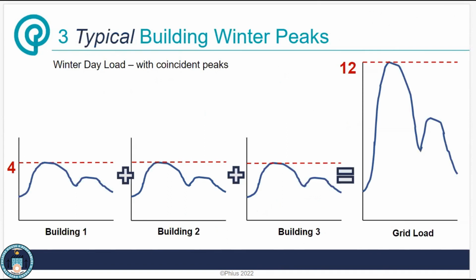And so when you add up all of the coincident peaks of typical operation buildings, if every building uses 4, just for easy math here, 3 buildings together have a peak coincident grid load of 12.